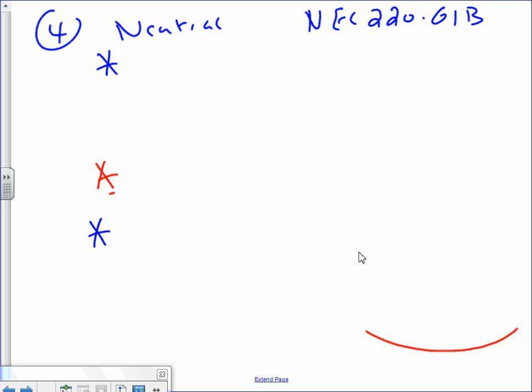Do me a favor. Can you guys go to NEC 220.61(B)? 220.61(B). 220.61(B), guys, if you read it, highlight it please, it will tell you, hey, if your neutral is more than 200 amp, that neutral that you're calculating can actually be cut again. You can cut it one more time. Reduce it, Brandon. Reduce it another 70%. If you guys read, anything more than 200, you can reduce it to 70%.